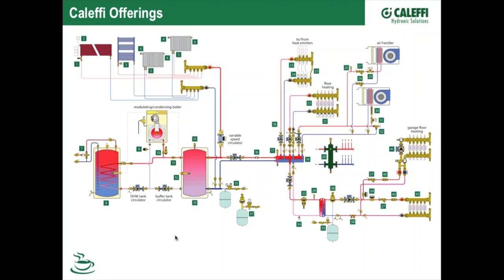Thank you. Another question concerning hardware around the boiler. Low water cutoffs. Are they needed? Are they built into the boiler? Yeah, excellent question, and I would say yes and yes. They are needed, and most of the boilers are going to require that you have one on. It's protecting the boiler, so if water leaks out of the boiler, or you have a problem or something like that, we want to shut that fire off before we cause damage.